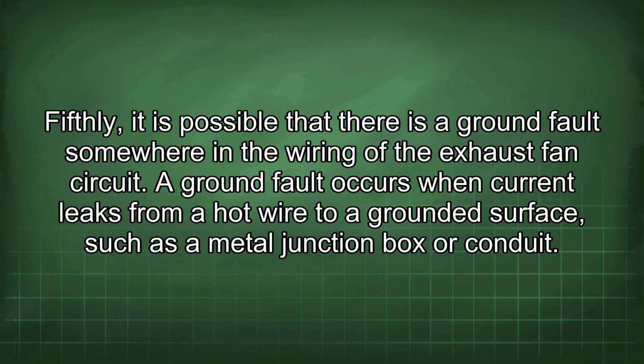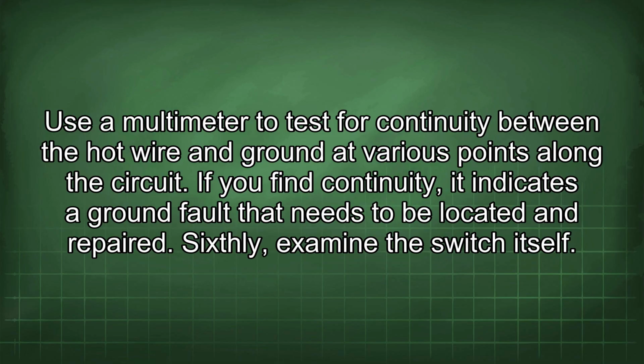Fifthly, it is possible that there is a ground fault somewhere in the wiring of the exhaust fan circuit. A ground fault occurs when current leaks from a hot wire to a grounded surface, such as a metal junction box or conduit. Use a multimeter to test for continuity between the hot wire and ground at various points along the circuit. If you find continuity, it indicates a ground fault that needs to be located and repaired.